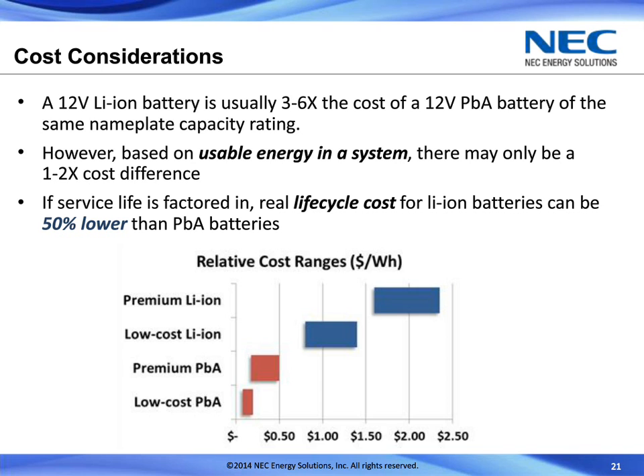And then if you look at that in terms of the actual life cycle cost for a lithium battery over a period of years, the longer life of lithium can actually come out to be as much as 50% lower than the lead-acid battery in the overall total cost. And the chart here gives a little bit of an indication of what the initial cost of the battery is based on nameplate dollars per watt hour. But that's not really the metric that you need to compare these against. It's really about what the cost of the overall system and the performance within that system actually is, and that's the key criteria.